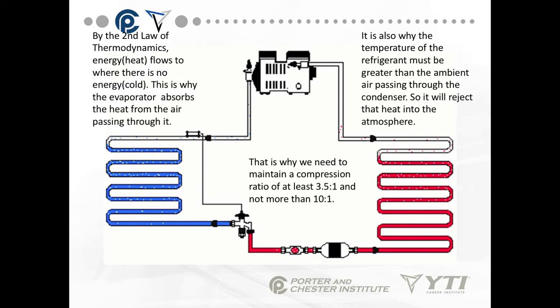On the outside system, we raise the pressure and raise the temperature so that heat will always flow out of the refrigerant into the air blowing across the condenser coil, rejecting the heat. That's why we need to maintain a compression ratio of at least 3.5 to 1 and not more than 10 to 1. The compression ratio basically describes the pressure coming in relative to the pressure going out.